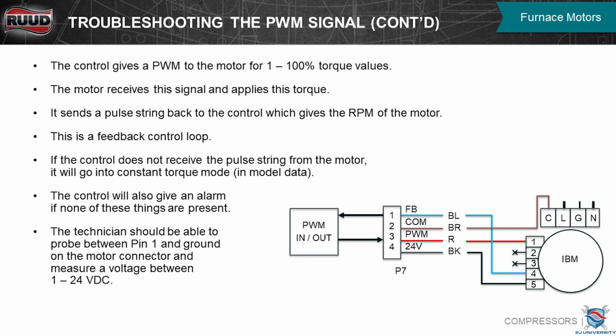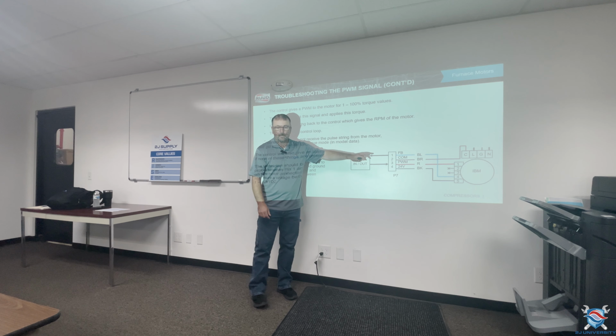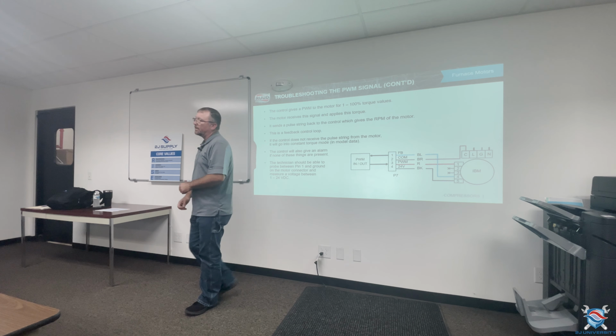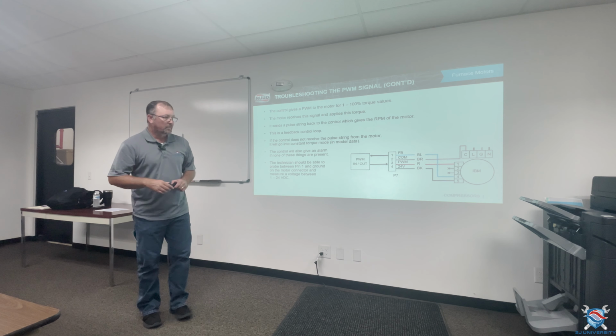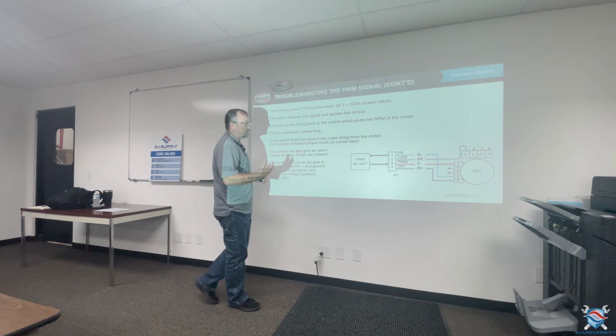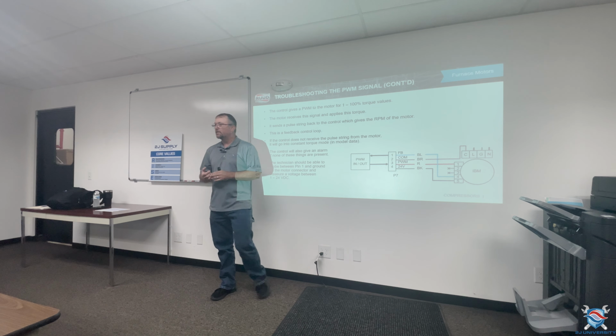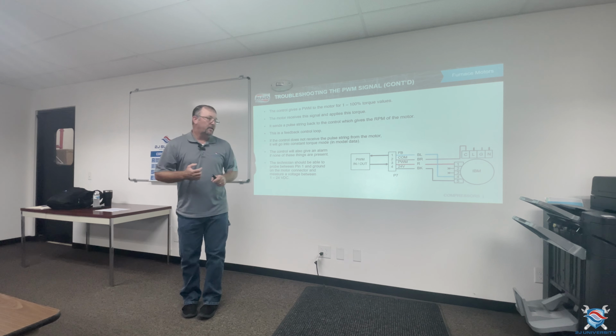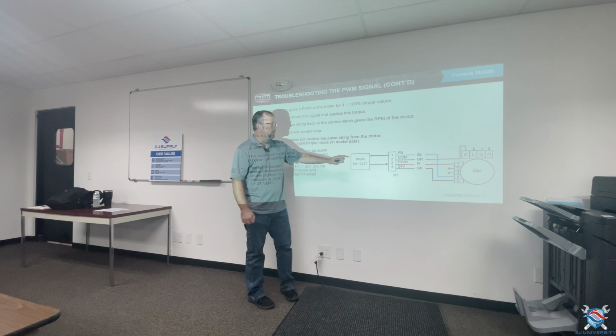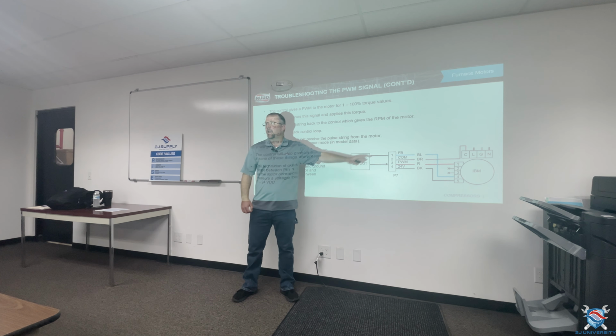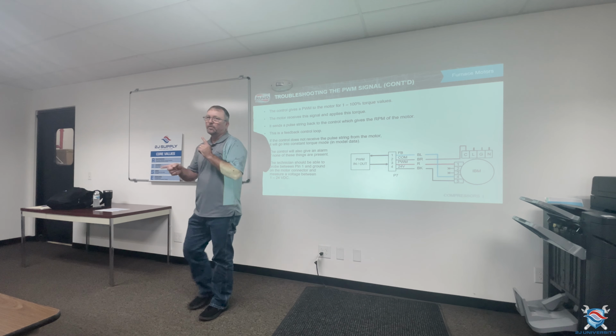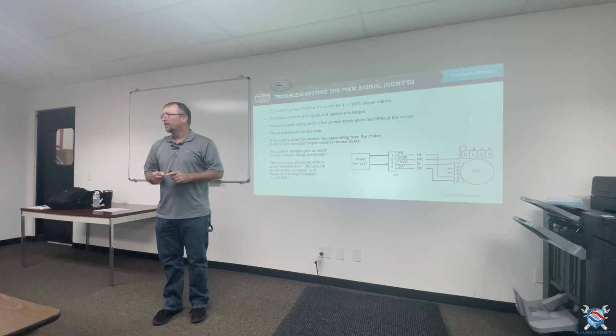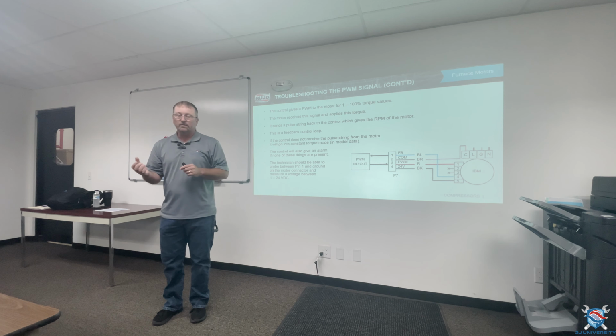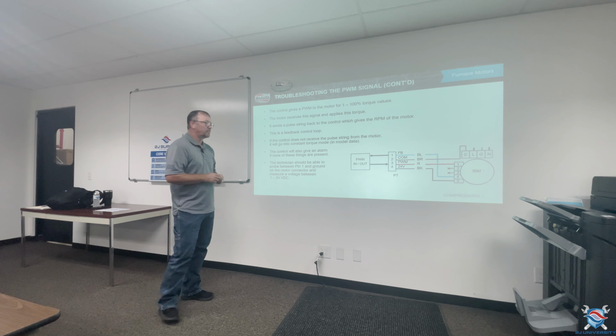But what they've changed in this is now it's a 4-wire pin connector that goes into this. What they've done is they've taken a constant torque ECM motor and they've added a PWM signal and a feedback signal so that it communicates back and forth. So they've taken a plain constant torque and now made it variable speed.